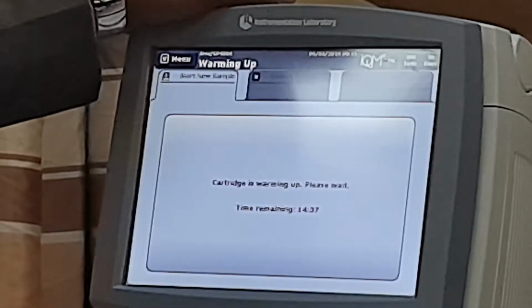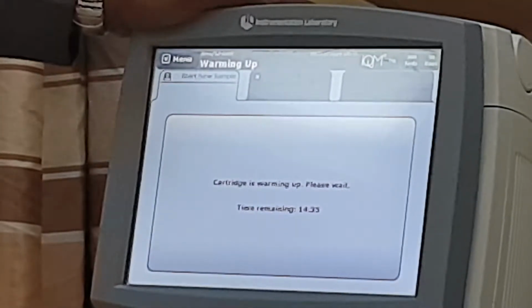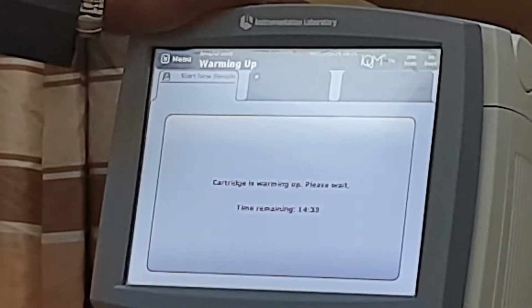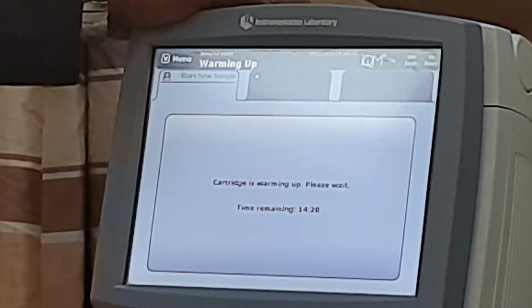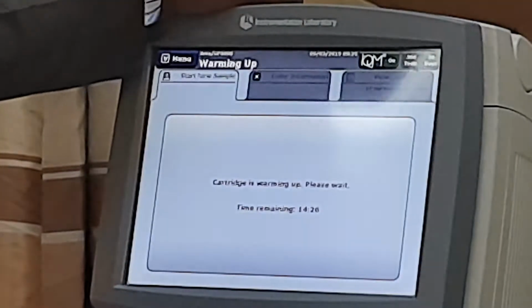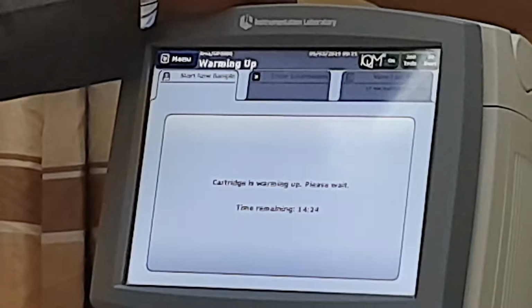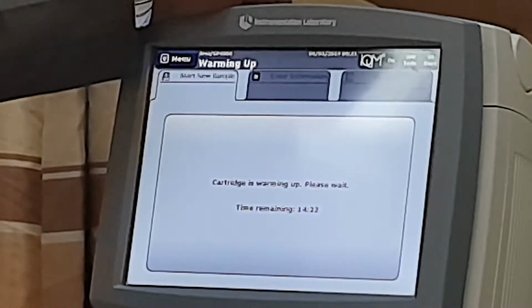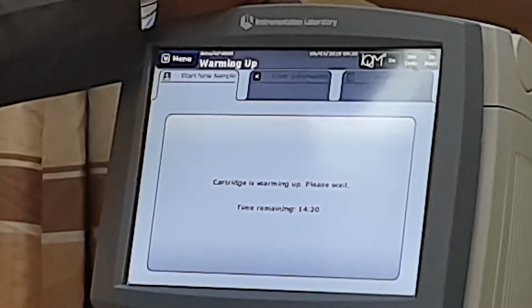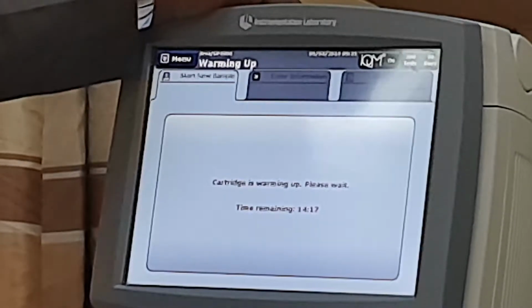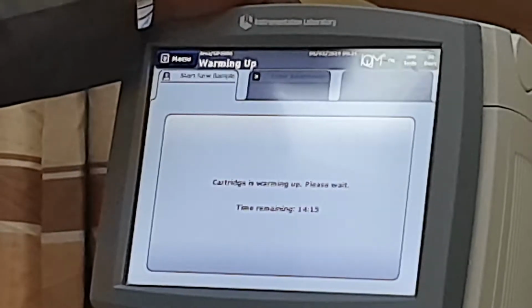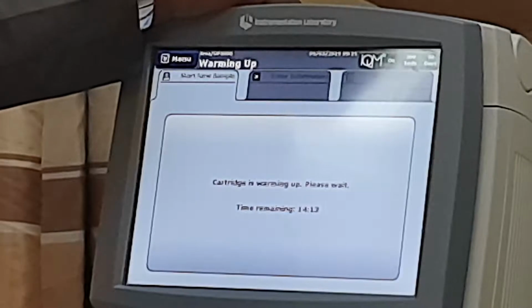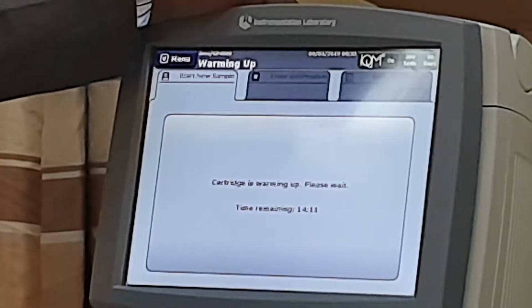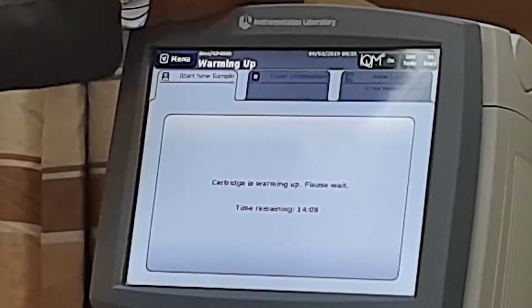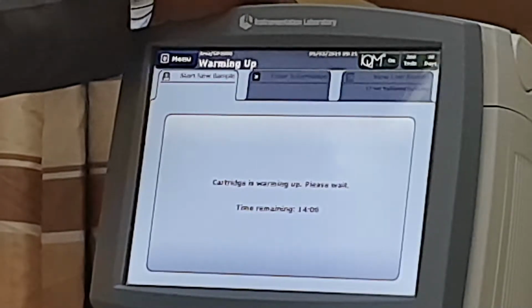For the volume, the minimum volume is 150 micron for each sample. That means if I have 200 micron or 250 micron, it will be okay. This is for the full panel. But for just co-oximetry, I will use just 75 micron. That means 2 drops of blood. It's nothing. So it depends on which type of panel you will use.